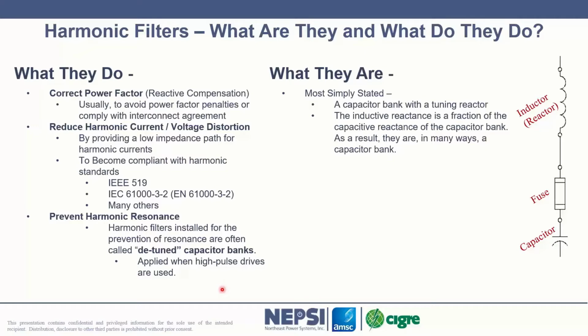Harmonic filters provide reactive compensation. They have a VAR output. To the right here, I show a notch harmonic filter. It consists of just the reactor and a capacitor. The purpose of that reactor is to tune this capacitor to a harmonic. Typically, the reactance, the XL of that reactor, is 1 over the tuning point squared of the capacitive reactance down here. So when you think about a filter, it is primarily capacitive at its fundamental frequency, 50 hertz or 60 hertz. So think of a filter bank as a capacitor bank.